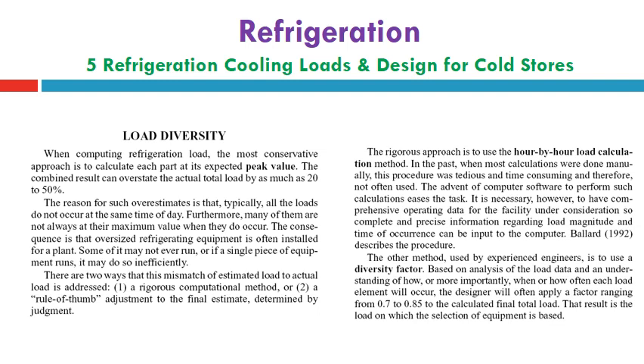Load diversity: when computing refrigeration load, the most conservative approach is to calculate each part of the expected peak value. The combined result can overstate the actual total load by as much as 20 to 50%. The reason for such overestimates is that typically all loads don't occur at the same time of the day. Furthermore, many of them are not always at their maximum value when they do occur. The consequence is that oversized refrigerating equipment is often installed for a plant.